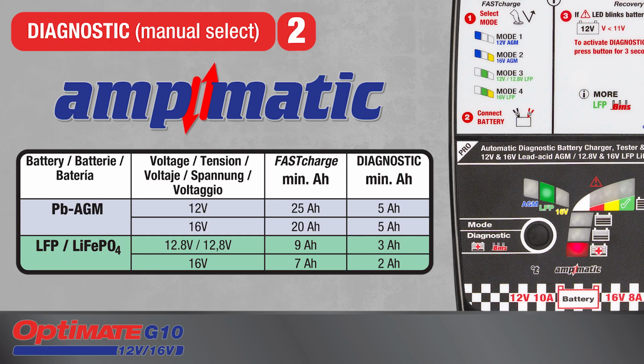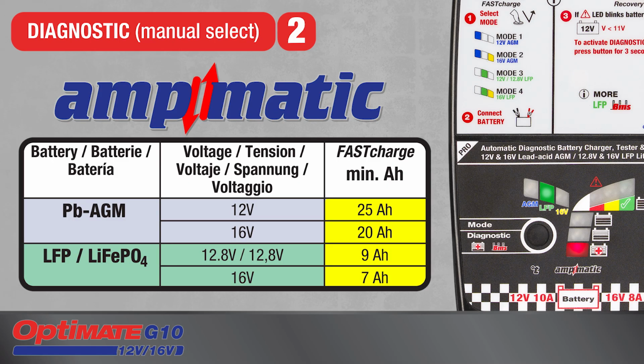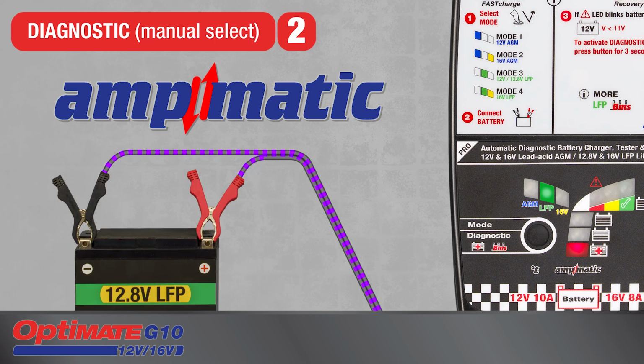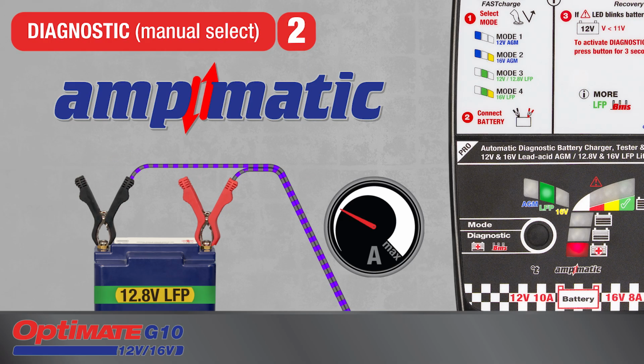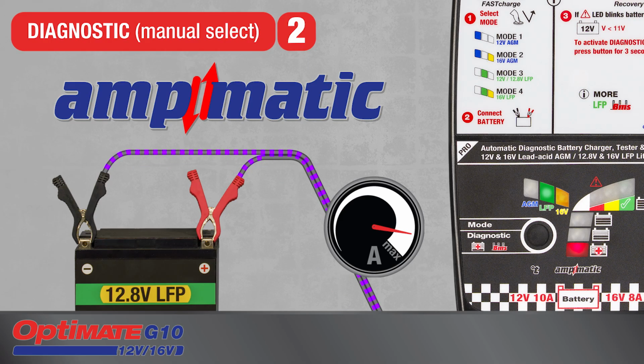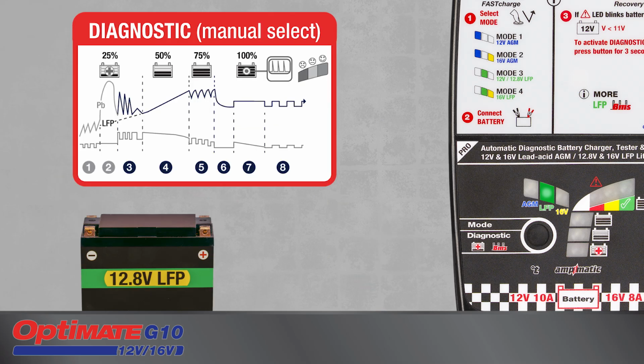Second, charge a battery with amp-hour capacity below the minimum value. During Diagnostic, Ampmatic current control is active, during which charge current is dynamically adjusted to match the battery's capacity. A smaller battery gets less, a bigger battery gets more. Diagnostic can be pre-selected prior to battery connection.